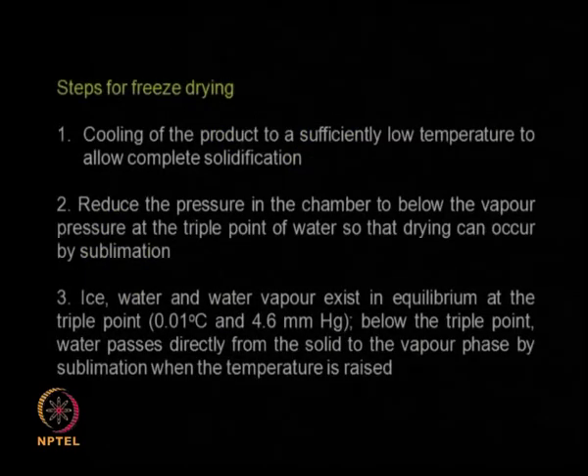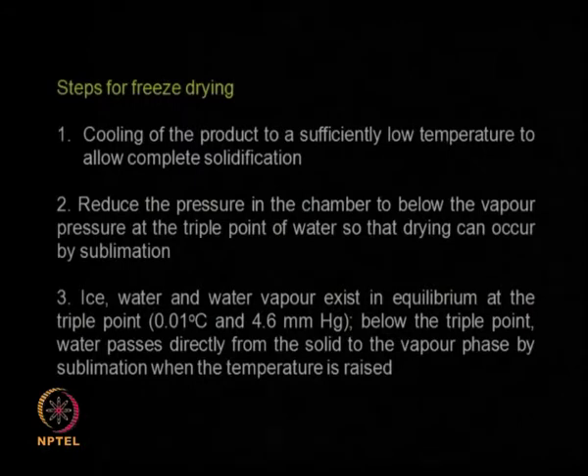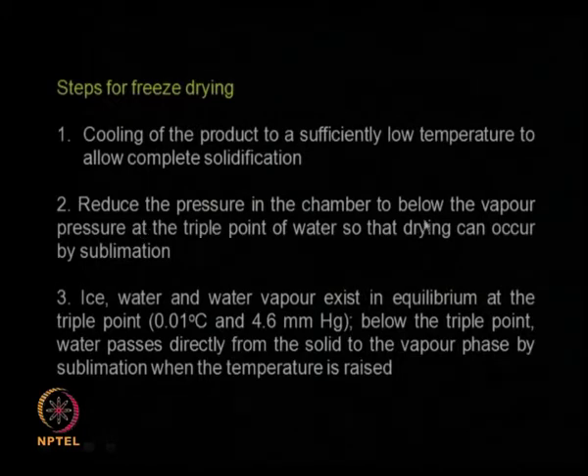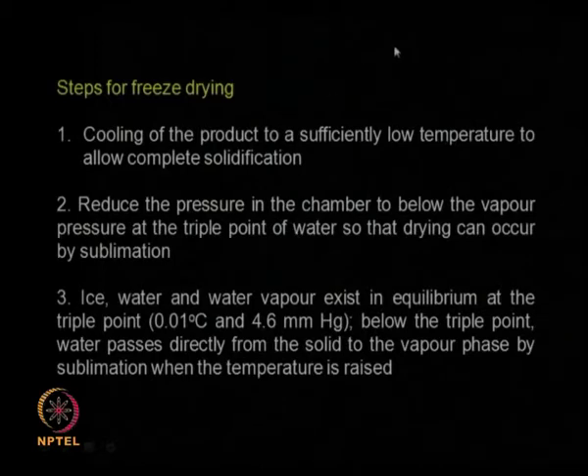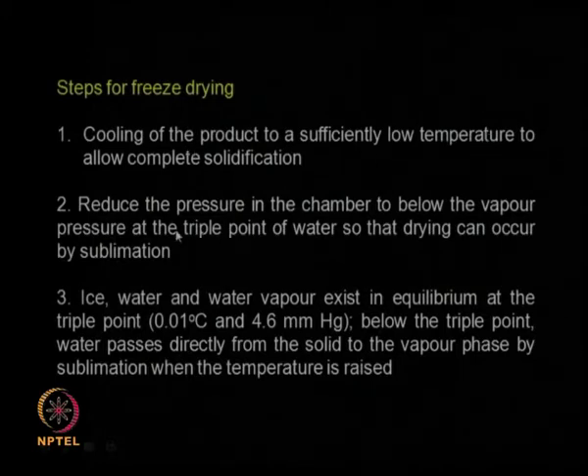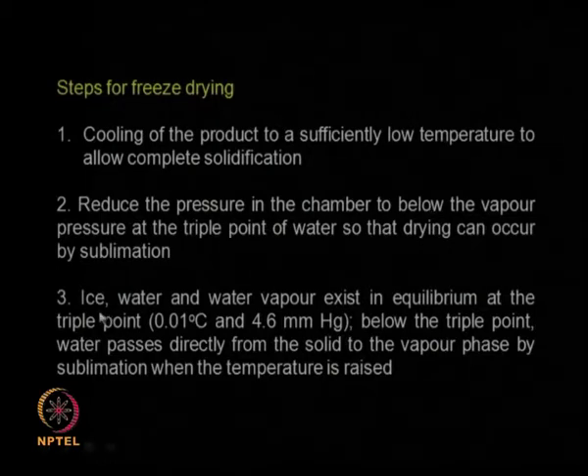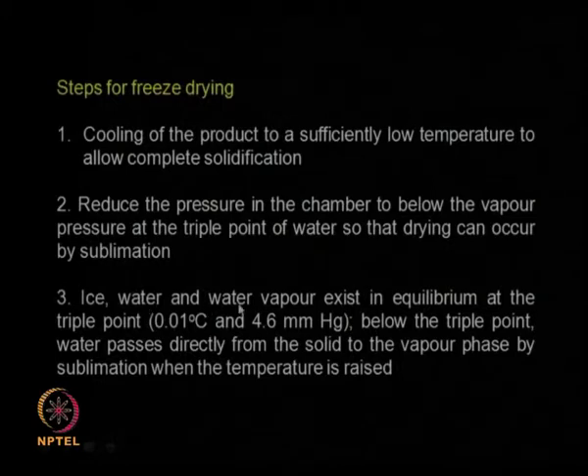The steps in freeze drying: first, you cool the product to a sufficiently low temperature, completely solidifying the material. Then you reduce the pressure in the chamber to below the vapor pressure at the triple point of water so that sublimation occurs — converting solid water into vapor. The triple point is at 0.01 degree centigrade and 4.6 mm mercury. Below this triple point, water passes directly from solid to the vapor phase — sublimation takes place.